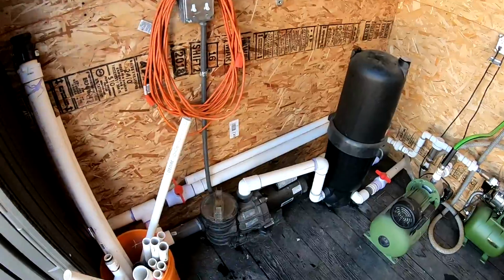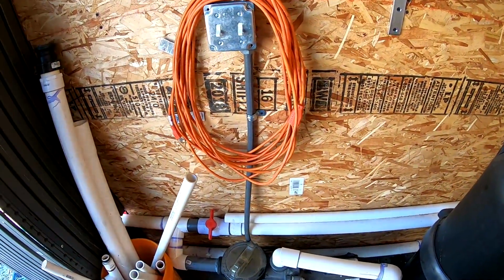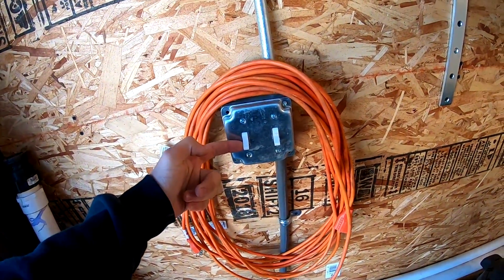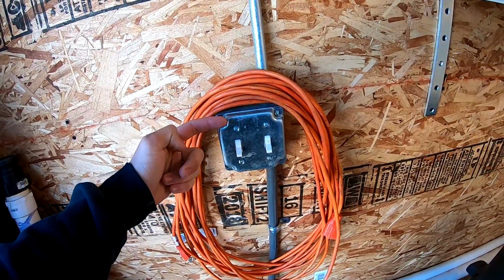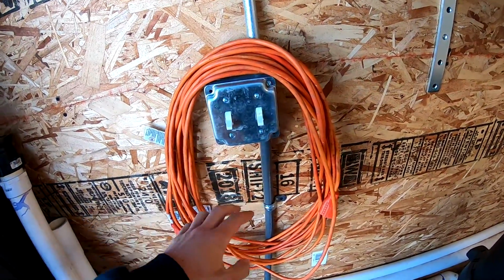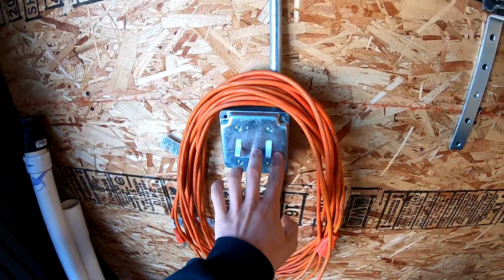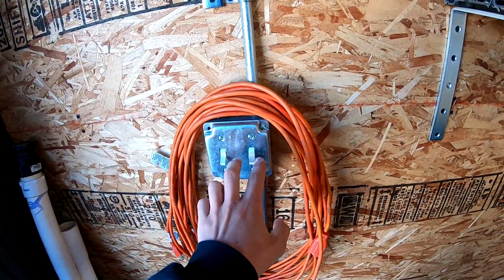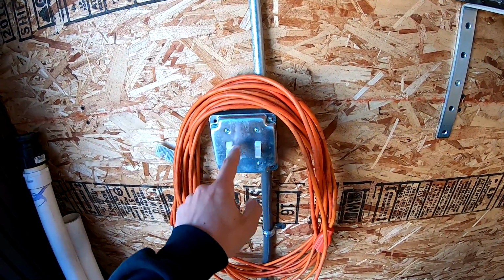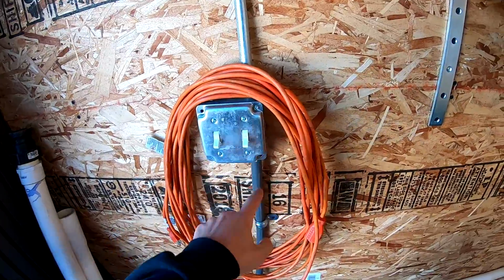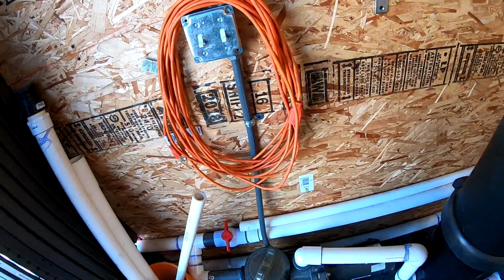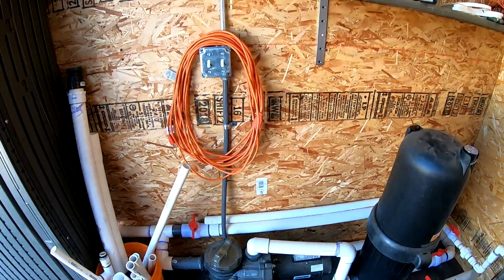And this is wired in. This is a 2-speed pump, so it has a low and a high. So I have a 3-way switch right here wired in. One direction is the low, one direction is the high. And then this is a 2-pole switch. So your two hots come in. One of the hots jumps over to the speed selector. The other hot goes down to the pump, and works out very nicely.